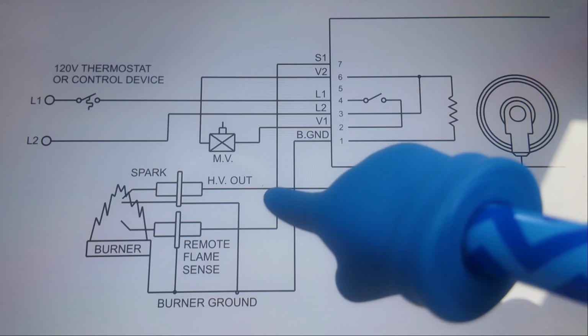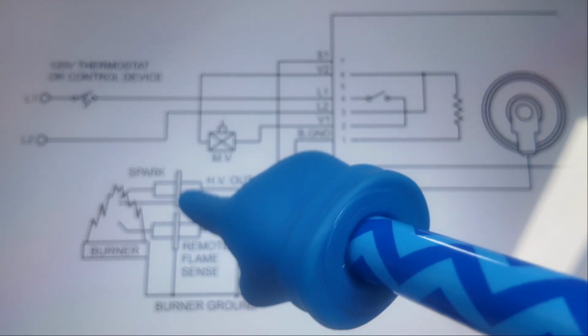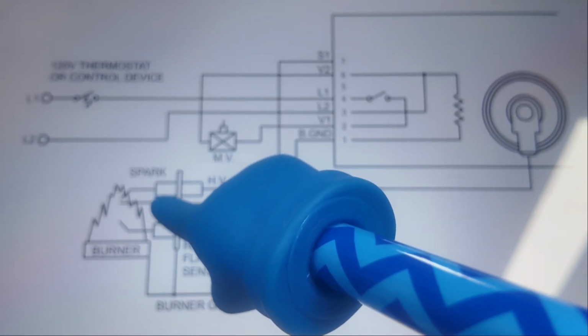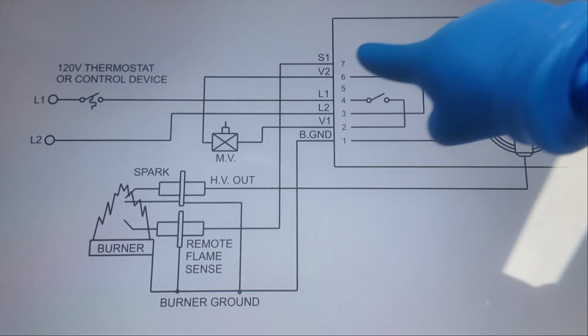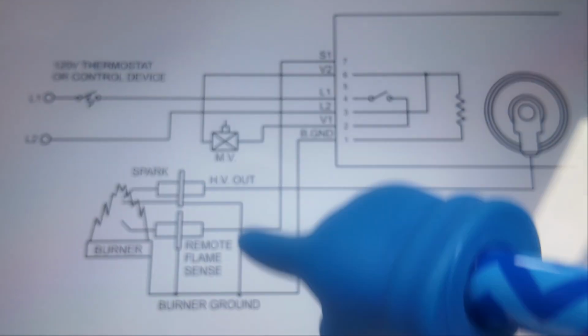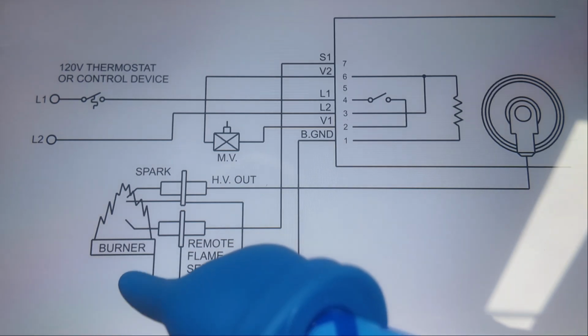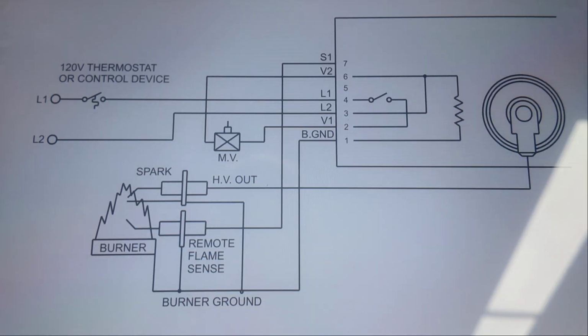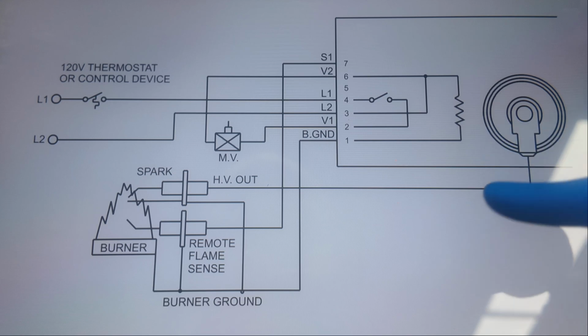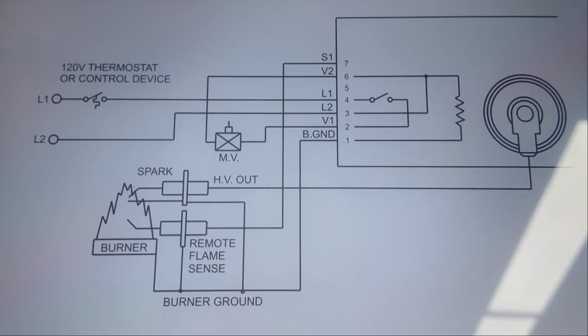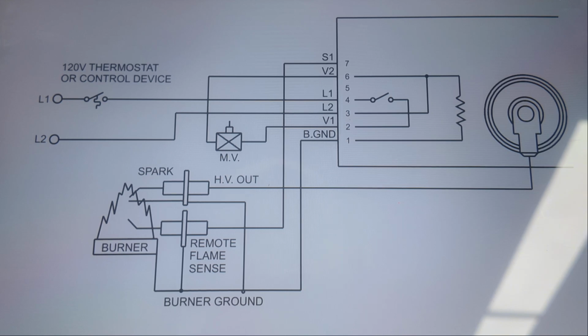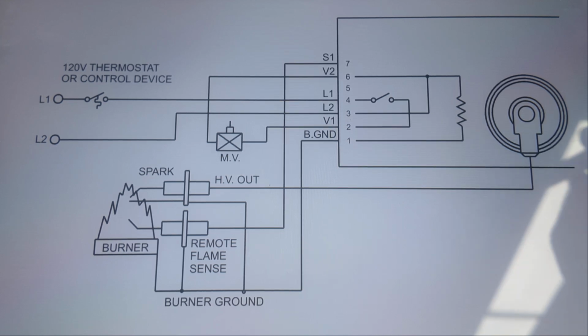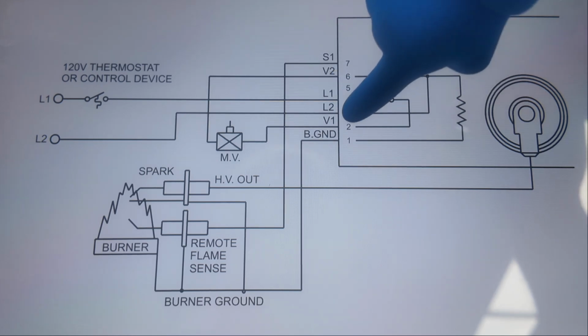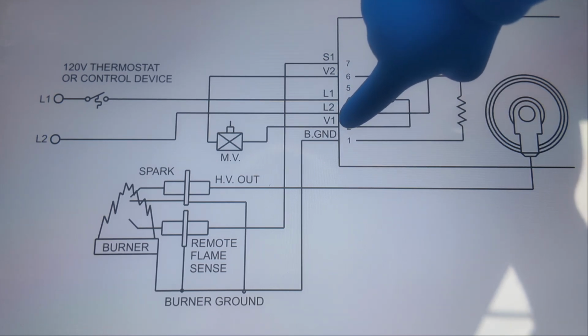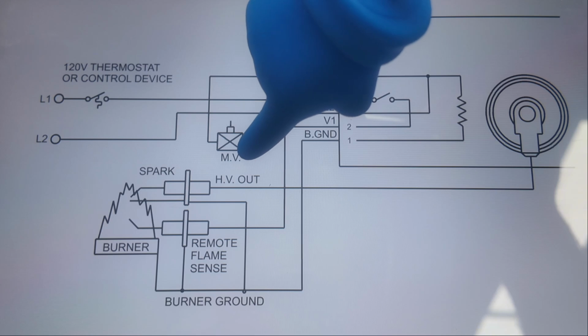I've seen it where S1 is connected to the ground probe here. That will burn out boards, because arcing off the sensor wire is going to burn out the board eventually. There's a lot of different configurations of wiring I've seen, but this is the correct way to wire your Fenwal board in your GSI or MC dryer.